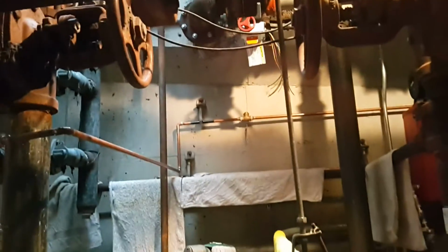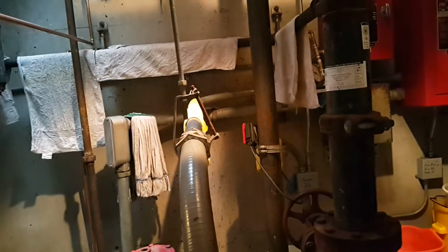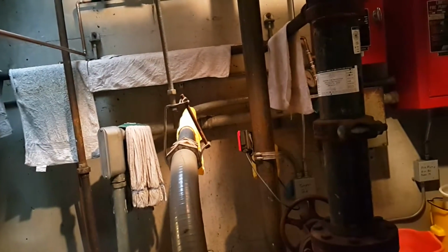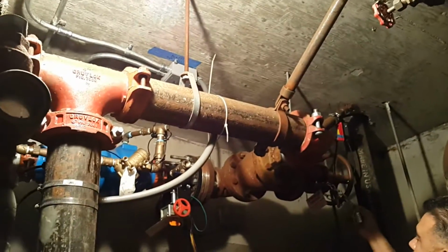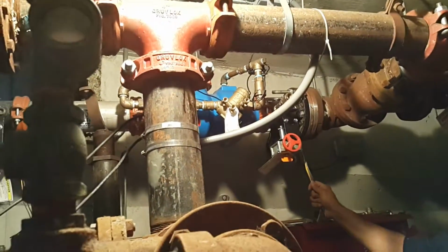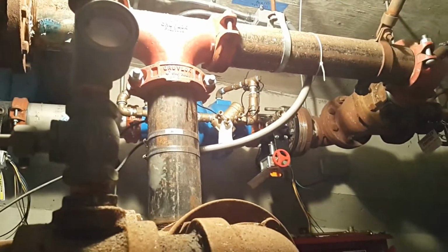There are three things that have to be true of these valves right here, and I made a note of it last year. They have to be either locked, sealed, or supervised. If they're locked open, you've got to have a lock and chain, to make sure they're open. That means nobody messes with it. Supervised, you can see the tamper device on this one right here, and then this one is locked also. So this lock should actually be on these two here, because these aren't monitored, which means they're not tied into the fire alarm system. So if I was to take this tamper valve off and close this valve, you'd get a signal at the fire alarm saying, hey, something is wrong down at the fire pump room, come check it out.